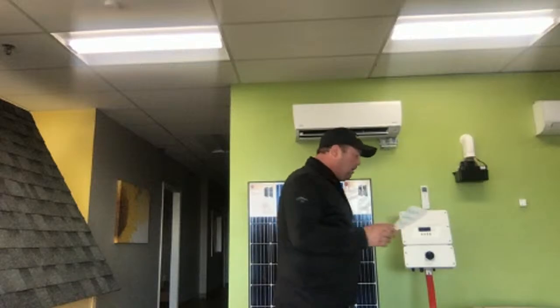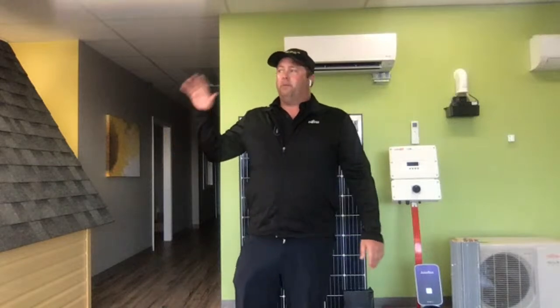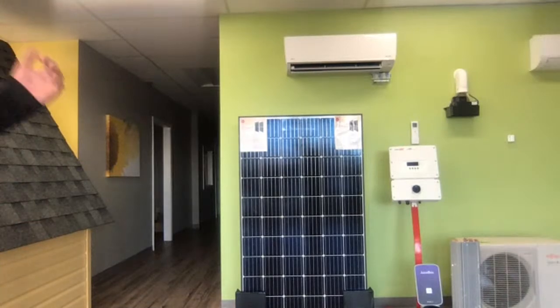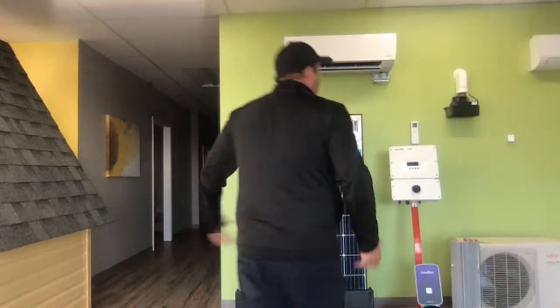How quickly does a ducted heat pump heat the house compared to a normal furnace? It all depends on the temperature. The colder the day, the bigger the difference. In the shoulder seasons, down to the end of December, it doesn't take long for the heat pump to heat up a house—you can do it in 10, 20 minutes. But if it's minus 15 or 20 outside and you turn the heat off for 5 hours and all the heat goes out, then turn the heat pump back on, good luck—it's not going to happen for a day or two, unless you use that primary heat to quickly get the temperature up, and then the heat pump can maintain it once achieved.